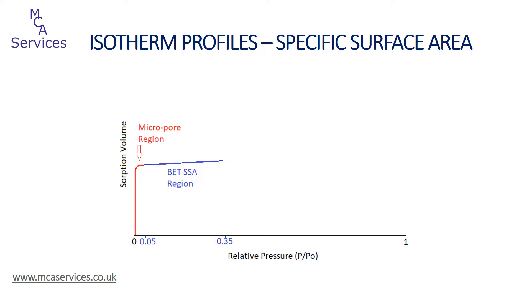Once the micropores are filled, further increases in relative pressure will result in the adsorbate gradually covering the external surface of the sample and forming a layer coating the internal walls of larger mesopores and macropores. This region is used to determine the specific surface area of the sample, most commonly using the BET model — more information can be found in our presentations on BET surface area. Essentially this portion of the isotherm covers the approximate range 0.05 to 0.35 relative pressure, representing the classical BET range in which monolayer adsorption occurs, which is critical to the calculation of BET surface area.